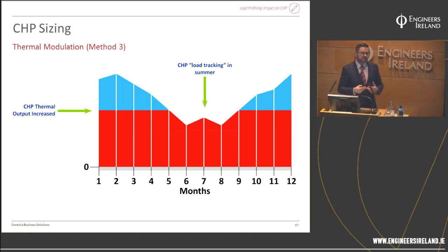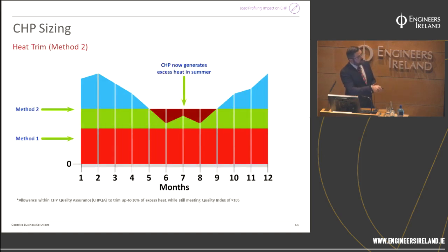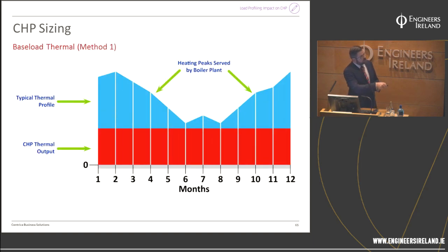It's still in the system, it's still in the engine, and if it doesn't get away, that could cause problems. So this is a situation that we wouldn't really promote, because we can have this in our back pocket. If we're going to design a smaller CHP at a lower capital cost, and say this year there was even less thermal requirement, then the CHP can modulate down here.